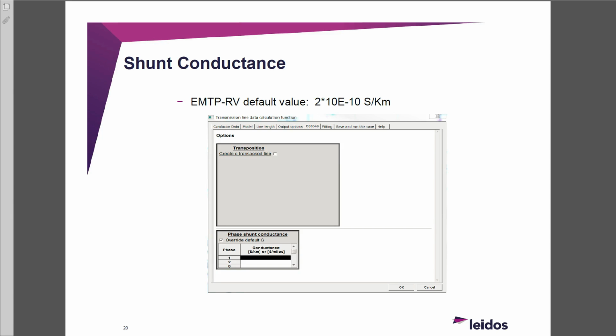So if you're using EMTP, it's okay - the default values are acceptable. But be careful with all the other software, and double check the numbers you use, because these will really change your TOV. Depending on the value you use, you'll either see no TOV or you will see TOV. So really be careful - using EMTP you're good on the number, but still double check it. If you have your own number, I'd recommend changing it.